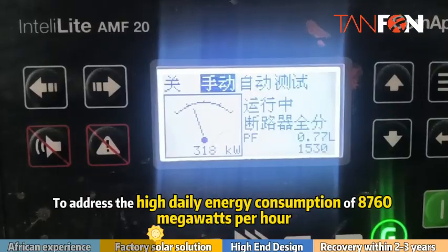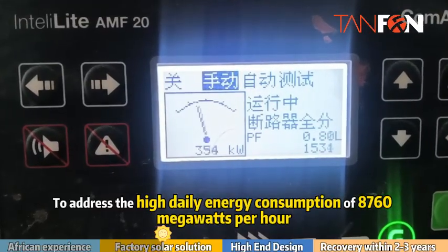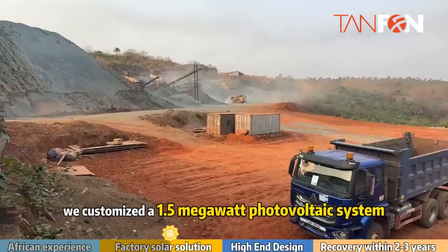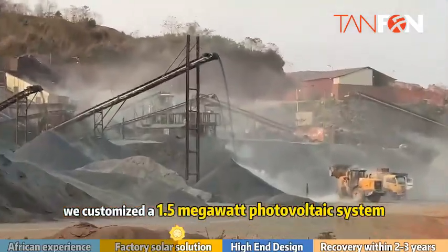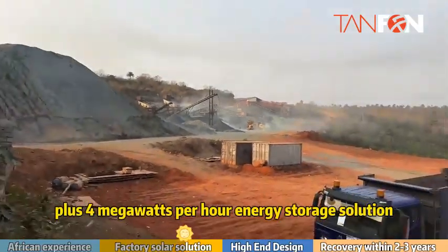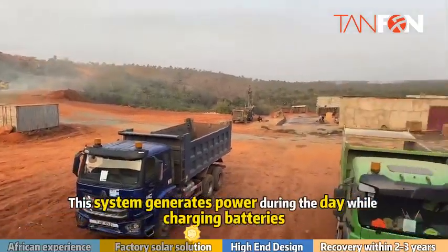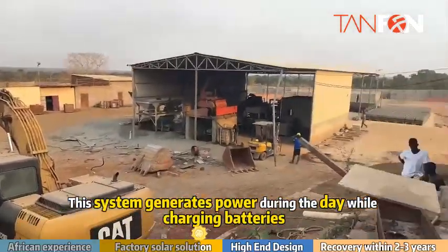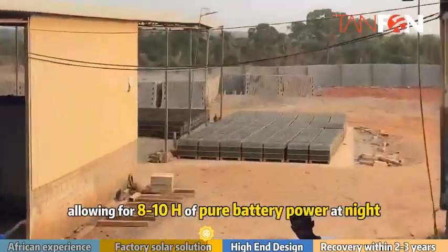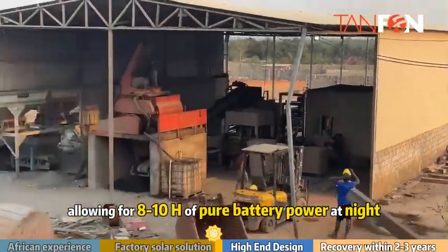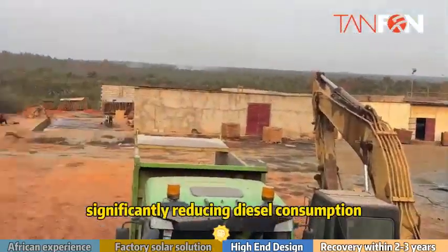To address the high daily energy consumption of 8,760 megawatt-hours, we customized a 1.5 megawatt photovoltaic system, plus a 4 megawatt-hour energy storage solution. This system generates power during the day while charging batteries, allowing for 8 to 10 hours of pure battery power at night, significantly reducing diesel consumption.